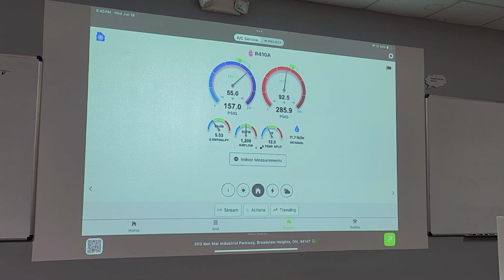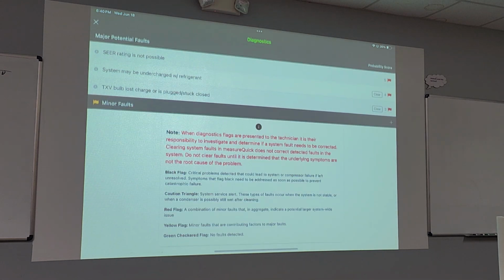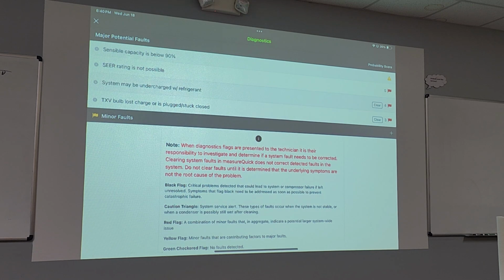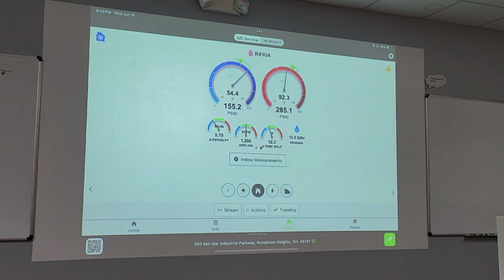When you see it displaying numbers like 1195, 1192, 1208, you know it's actually calculating the airflow live in real time. But when you have certain faults on the system, like the undercharge condition, and just the high... we have psychrometric charts loaded into this thing. And so if you're outside of the range of the psychrometric charts, it can't make those calculations. At least that's my understanding of it.